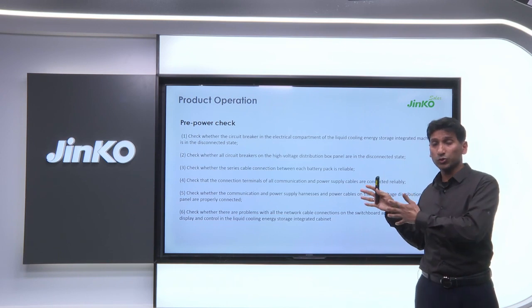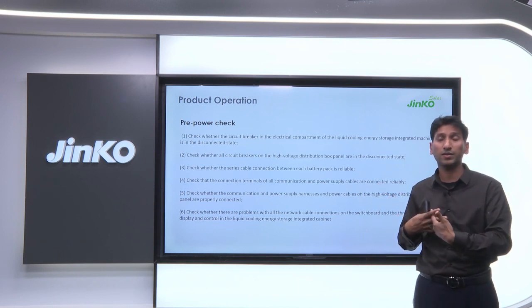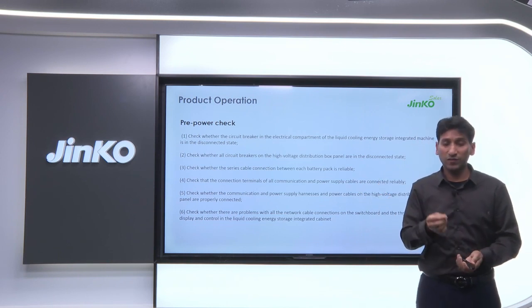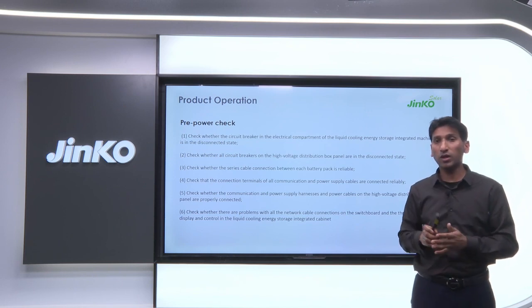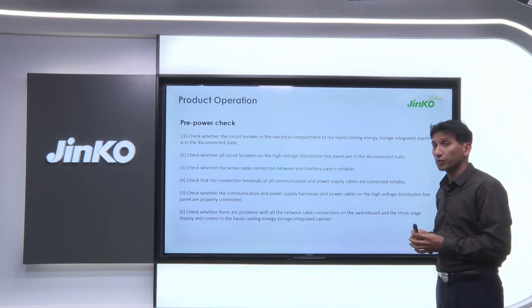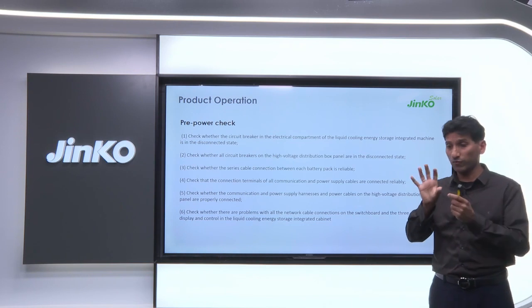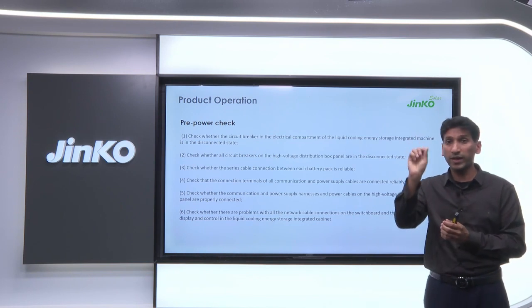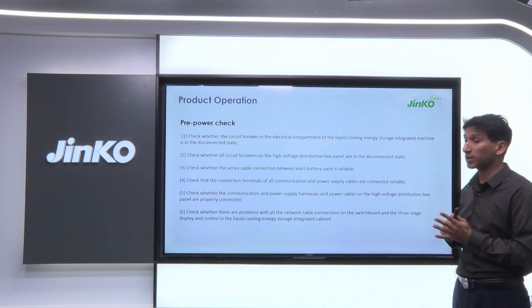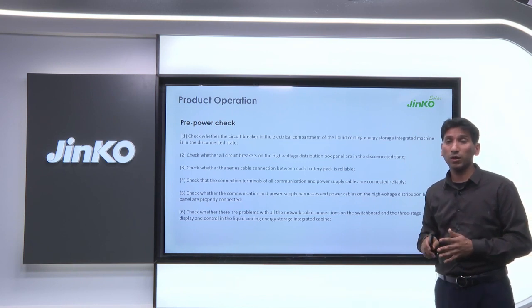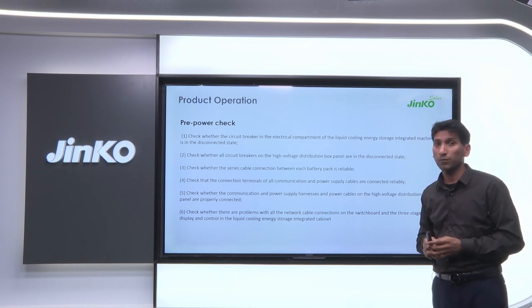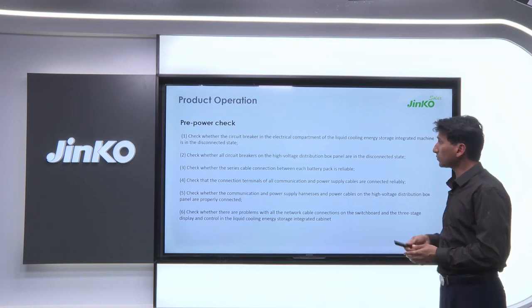Even though the fault is showing this, everything is still connected. And finally, we find out that there's one wire that was not fully connected. So when you are doing the check, you also have to check everything by hand, not fully by hand, but you have to cover and check all the connections, that everything is made right. Otherwise, it's going to be a lot of trouble when you power up and the system is not working.